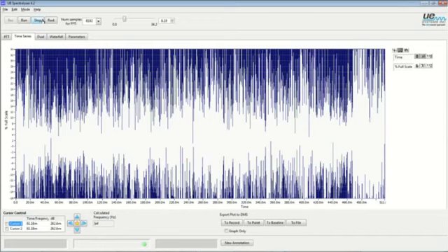Sure. Just for the benefit of those that may not understand the term tracking, the easiest way to think of this fault in an electrical system is that it's known as baby arcing. Tracking occurs when there is a breakdown in the properties of the insulator and it's unable to contain the stress of the voltage.